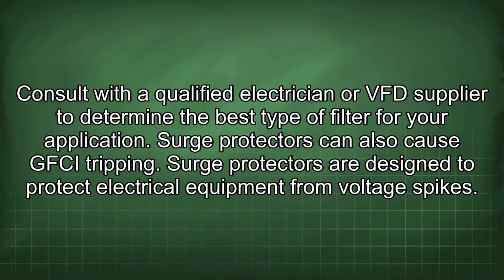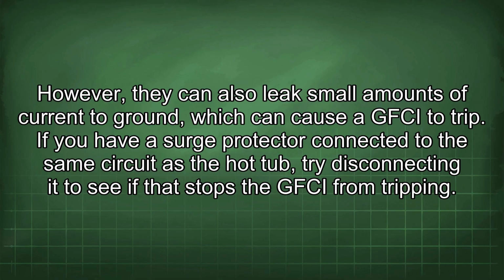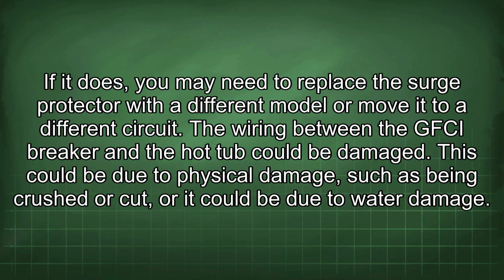Surge protectors can also cause GFCI tripping. Surge protectors are designed to protect electrical equipment from voltage spikes. However, they can also leak small amounts of current to ground, which can cause a GFCI to trip. If you have a surge protector connected to the same circuit as the hot tub, try disconnecting it to see if this stops the GFCI from tripping. If it does, you may need to replace the surge protector with a different model or move it to a different circuit.